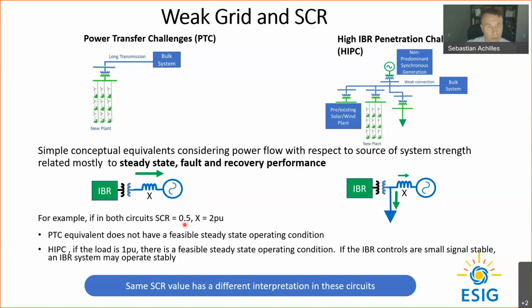If we, for example, say that the short circuit ratio is 0.5, I know this number sounds crazy because we typically talk about numbers higher than 1. If the short circuit ratio is 0.5, it means that this reactance will be 2 per unit on the base of the inverter-based resource. So let's assume that. The short circuit ratio is 0.5, and this reactance is this big. The system on the left is basically completely unfeasible. It's just not possible in steady state to push 1 per unit power through a system with this short circuit ratio if the voltages are reasonable. The system on the right, on the contrary, does have a possible steady state operation. So you could have this system being stable in steady state with a short circuit ratio of 0.5. What this means is that, depending on what kind of scenarios we're looking at, a short circuit ratio of 0.5 could mean a clearly unstable, impossible, not feasible condition, or a potentially feasible condition. So the same SCR means something different in these two systems.